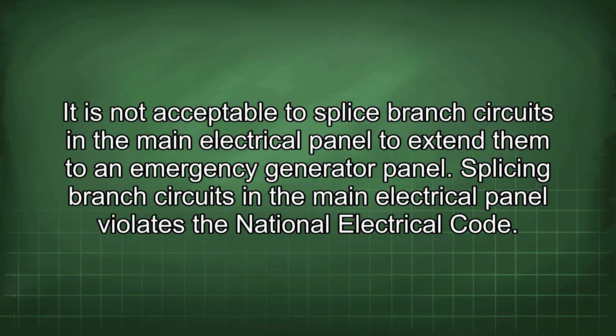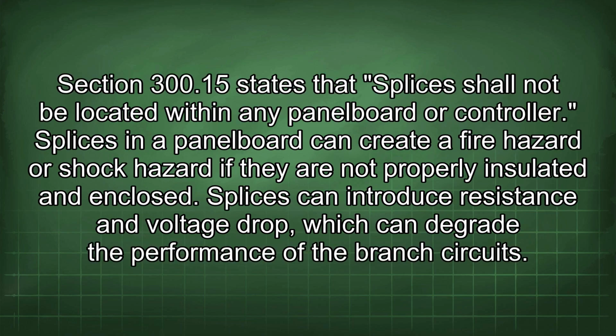It is not acceptable to splice branch circuits in the main electrical panel to extend them to an emergency generator panel. Splicing branch circuits in the main electrical panel violates the National Electrical Code. Section 300.15 states that splices shall not be located within any panel board or controller.